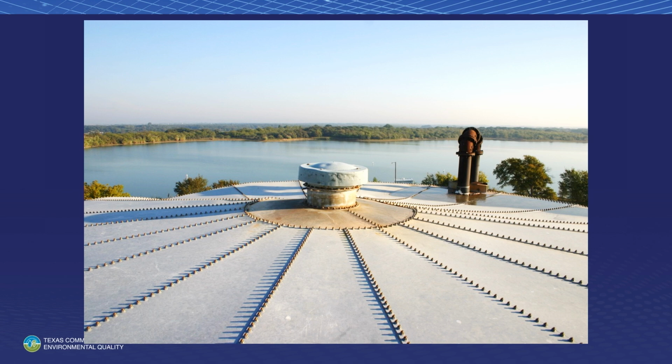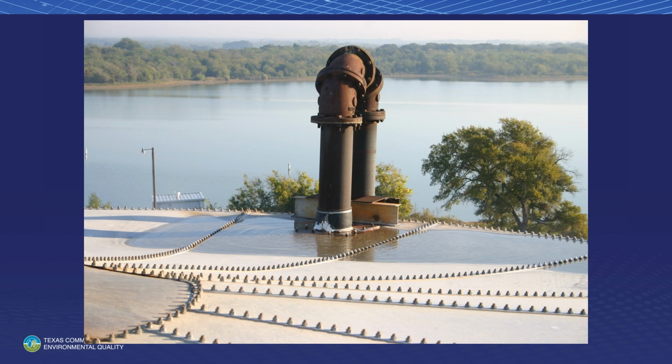Now that's the inlet to the tank, but the top of the tank around that inlet has collapsed. And you can see water, well, maybe you can't see it too well, but it's actually bubbling up around the point where that pipe enters the top of the tank. So there's a problem with contamination at that point to the ground storage tank.